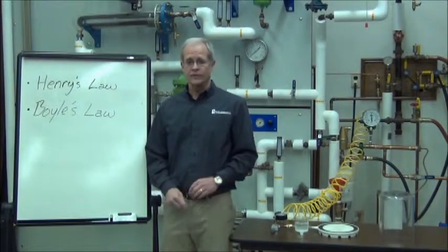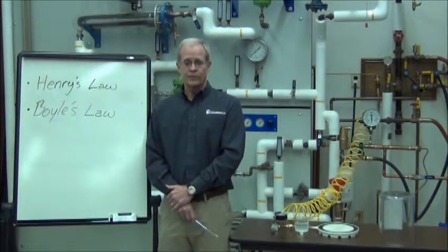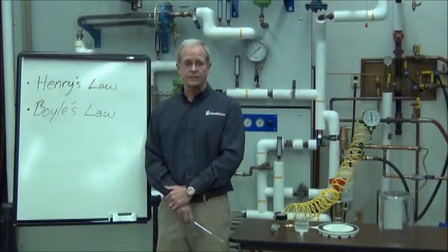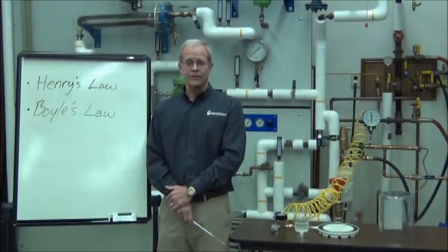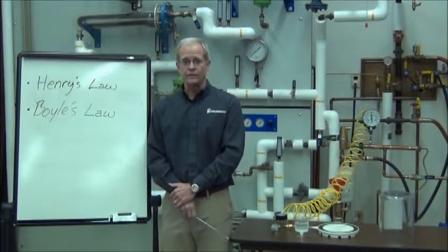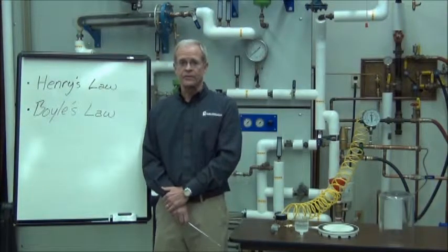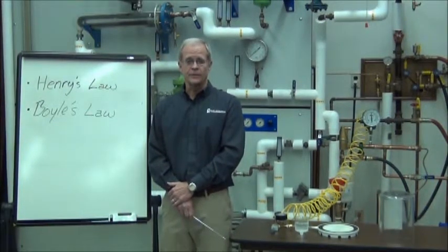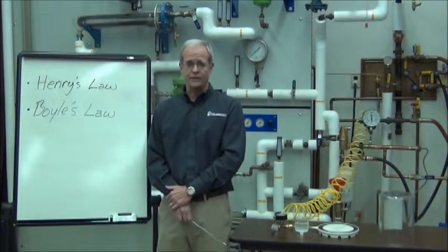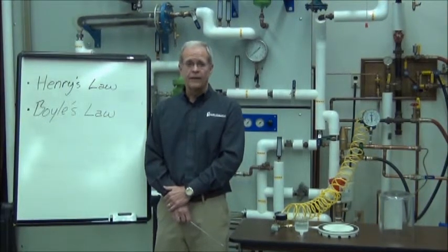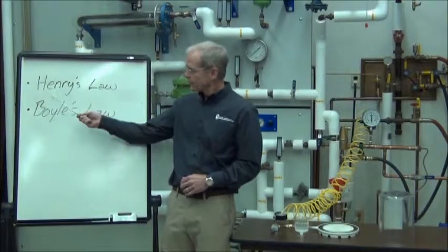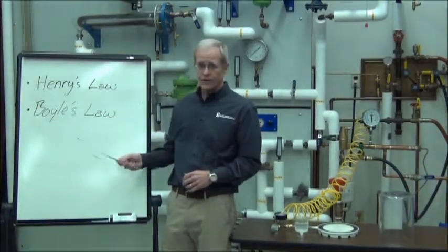What we're going to talk about in this video is a couple principles that affect pump selection in applications where you have a significant amount of air entrained or dissolved in the water. And that would typically be a cooling tower application because the way a cooling tower works results in a lot of air in the water. Those two principles are Henry's Law and Boyle's Law.